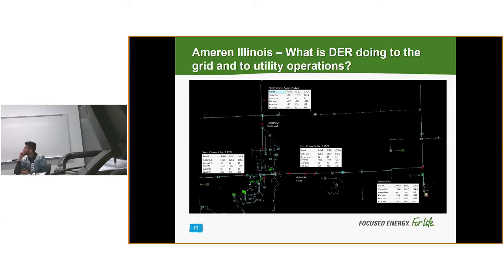So reconductoring is one thing we typically look at. One thing we'd ask the customer right off the bat: can you reduce your overall production on the circuit? Instead of 2 megawatts or 2 MVA, can you do 1.85? We'll run a simulation to see what 1.85 will do, and if that solves your problem, we'll go back to the customer and say, can you put some control logic on top of your inverter, or in your inverter, to reduce and limit the amount of kW you want to produce?